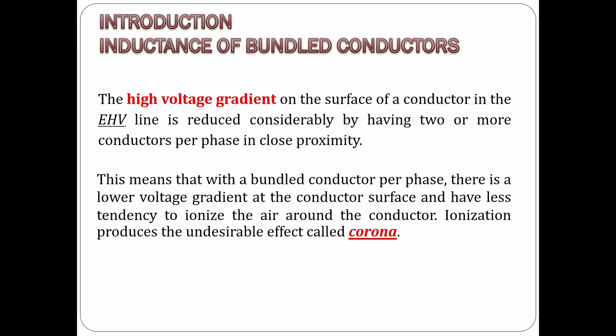In theory and in actual practice, the high voltage gradient on the surface of the conductor in EHV lines, or extra-high voltage lines, is reduced considerably by having two or more conductors per phase in close proximity. This means that with a bundled conductor per phase, there is a lower voltage gradient at the conductor surface and less tendency to ionize the air around the conductor.